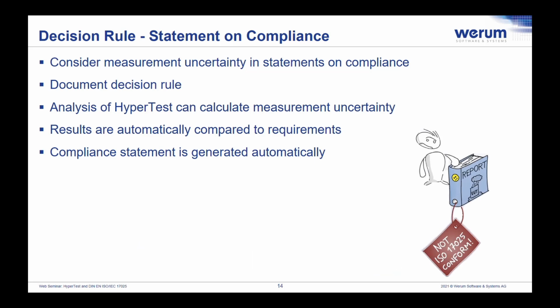The conformity statement can be generated automatically by the analytical functions of HyperTest, or it can be entered by the user. Here again, HyperTest will make sure that all relevant data and documents are properly assigned to the correct test or calibration order to ensure unambiguous traceability.